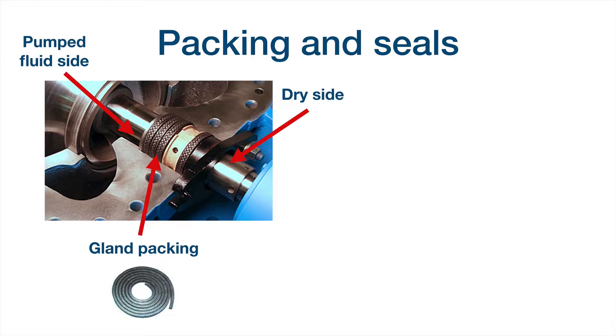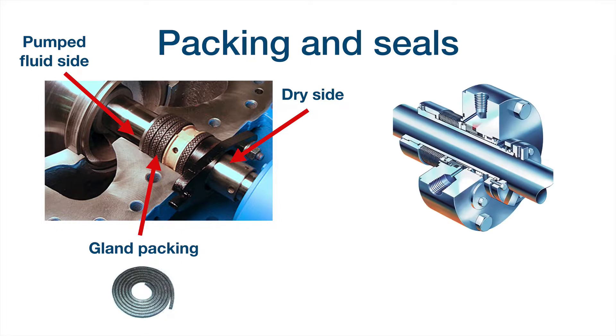Sometimes packing rings are overtightened by maintenance people trying to eliminate leakage entirely — but please note: there will always be leakage through the gland packing. This is normal. Do not overtighten. To achieve a lower level of leakage, mechanical seals are used. Here you have a mechanical seal — of course it has more components, is more complex, and the price will be higher, but you will not have visible leakage.